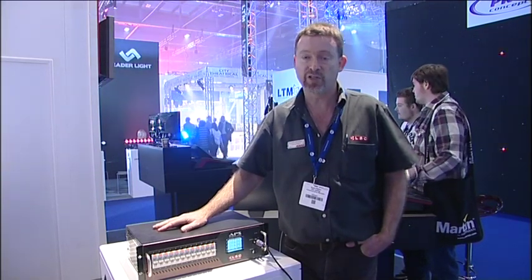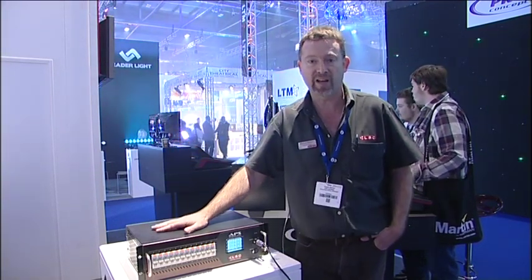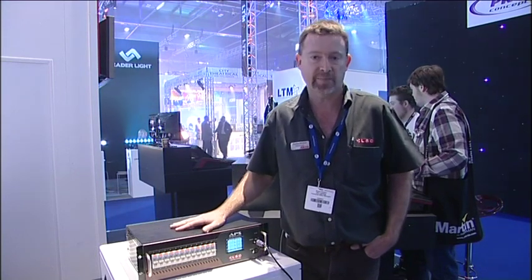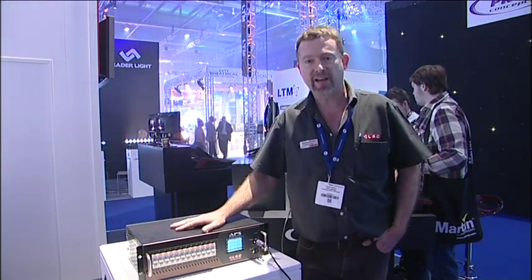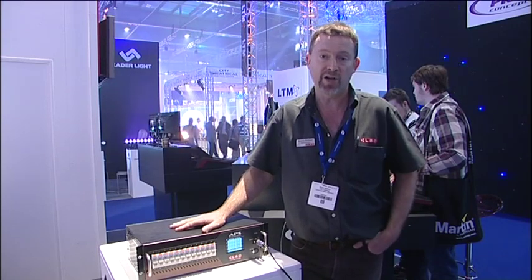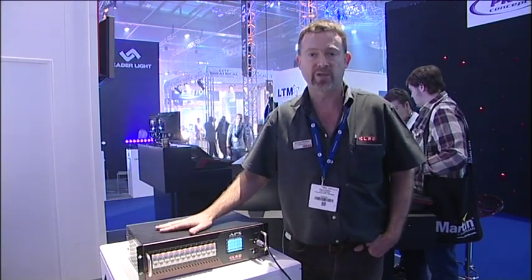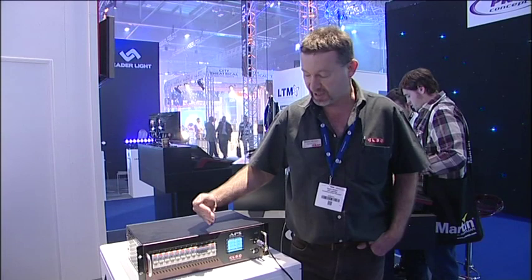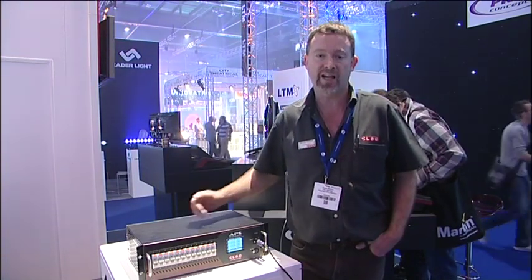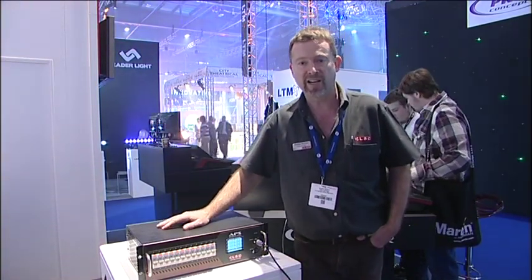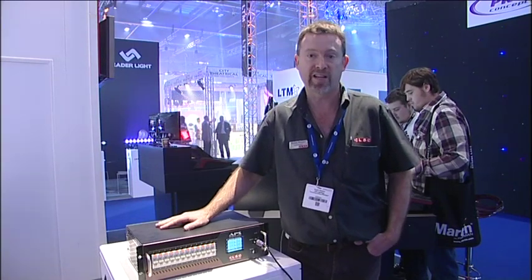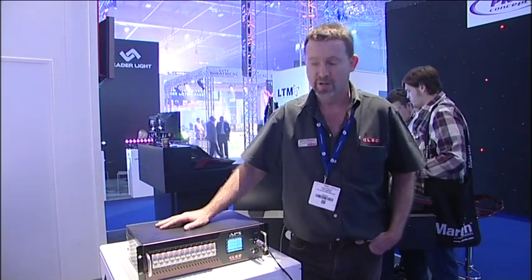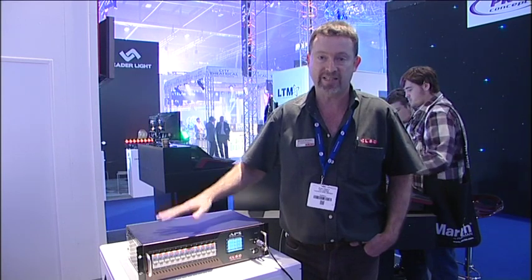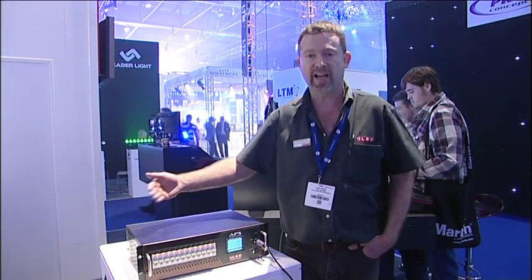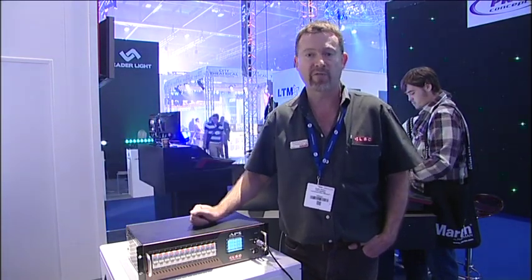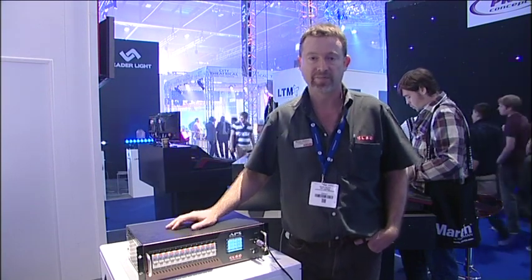In a lighting environment, as soon as a valid DMX signal is received from the lighting console, the APS starts its power-up sequence. It doesn't matter if the DMX signal is a DBO, it's just the valid DMX signal that starts the sequence. And each channel is sequentially turned on with a short time delay in between each one to prevent inrush current tripping circuit breakers or RCD devices. Multiple APS units can be stacked together and they'll automatically configure so that after the first unit starts up, subsequent racks automatically start their sequence as well.